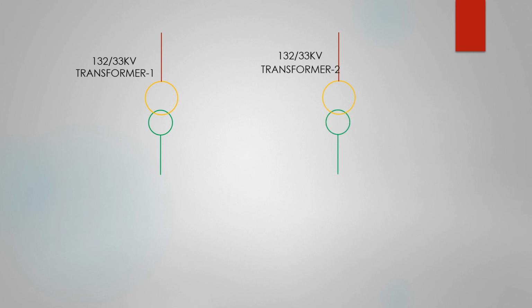Please watch. These are two 132 by 33 kV transformers. We suppose transformer 1 and transformer 2. The vector group of both transformers is YN D1. That is, both transformers have a star connected primary and a delta connected secondary. Both star connected primaries have the neutral point earthed, but the delta connected secondaries of the two transformers have no neutral points to earth.